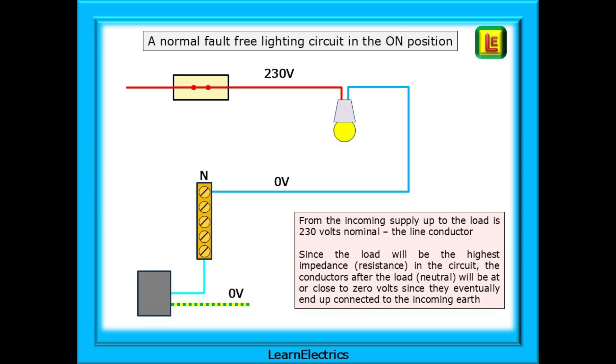We should begin with the normal, fault-free circuit in the on state, the switch in the closed position. From the incoming supply up to the load is 230 volts nominal, the line conductor. Since the load would be the highest impedance or resistance in the circuit, the conductors after the load, the neutral, would be at or close to 0 volts since they eventually end up connected to the incoming earth.